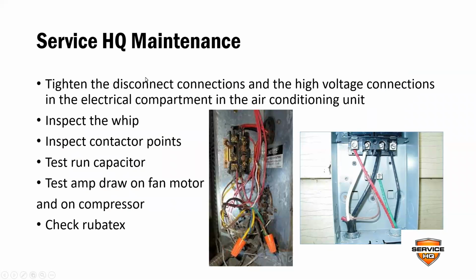As far as our maintenance, at this point, we're going to tighten the disconnect connections and the high voltage connections in the electrical compartment in the air conditioning unit. Inspect the whip, inspect the contactor points, test the run capacitor, test amp draw on the fan motor and on the compressor. And then we're going to check the Rubatex, Armaflex. That is the insulation on your suction line. You've got refrigerant lines, 2 copper refrigerant lines that come out of the house and tap into your unit, while the big line is your suction line, and that thing needs to be insulated. So we just check that.